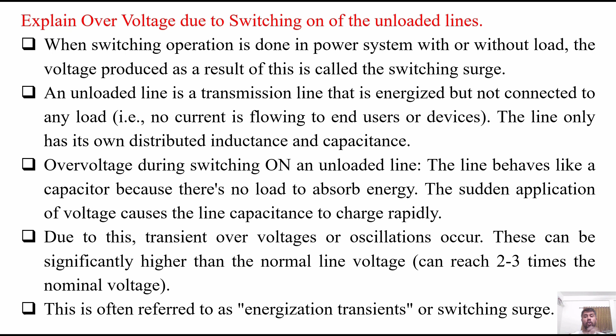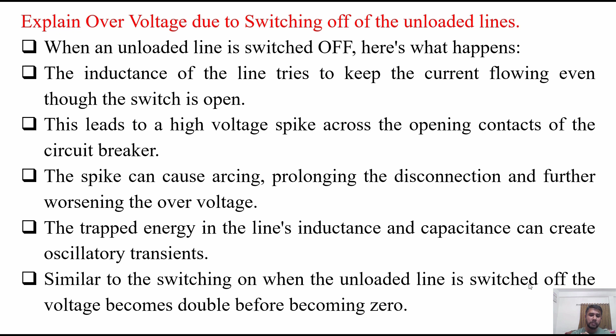Explain overvoltage due to switching off of the unloaded lines. When an unloaded line is switched off, here's what happens. The inductance of the line tries to keep the current flowing even though the switch is open. This leads to a high voltage spike across the opening contacts of the breaker. The spike can cause arcing, prolonging of the disconnection and further worsening the overvoltage. The trapped energy in the line's inductance and capacitance can create oscillatory transients. Similar to the switching on of the unloaded lines, when the unloaded line is switched off, the voltage becomes double before becoming zero.